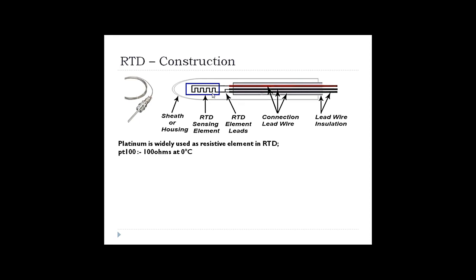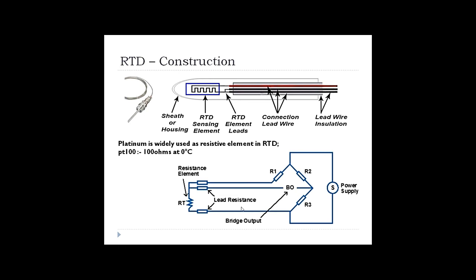Platinum is widely used as the resistive element in RTD. We call it Platinum-100 or PT-100. PT-100 means it provides 100 ohms resistance at 0 degrees Celsius. PT-200 would provide 200 ohms resistance at 0 degrees Celsius. So the RTD is used to measure temperature — if the temperature is 0°C, the output of the RTD will be 100 ohms.